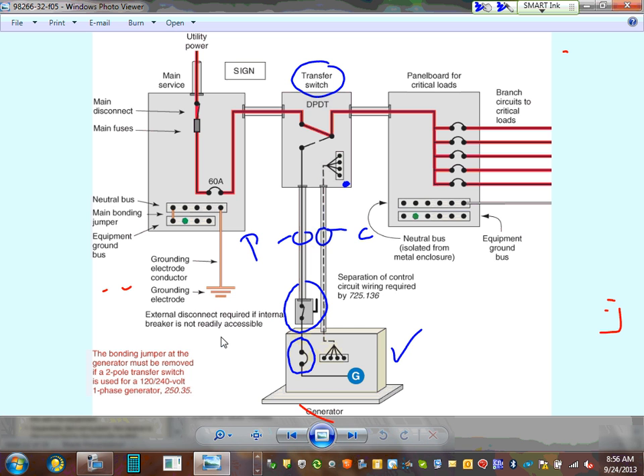It will sense that the power has been lost here. It looks at the power here. When the power is lost, guys, it will send a signal to the generator to start. That's what an auto does. The generator starts, and when it starts, it flips the power here. It flips that switch automatically. You don't have to do anything. It flips you from the utility over to the generator. Now everything in this panel is being powered by the generator. That's the auto. There's also a static transfer switch. The only difference is static is faster. It doesn't interrupt the power.